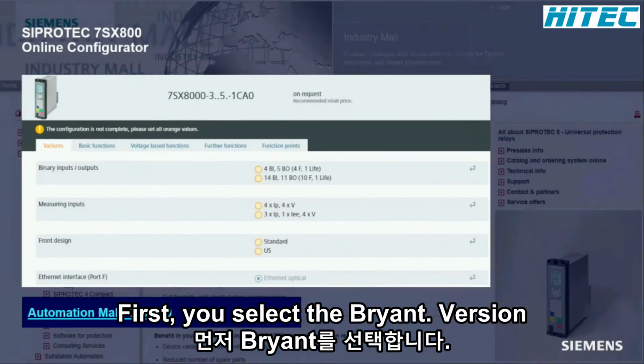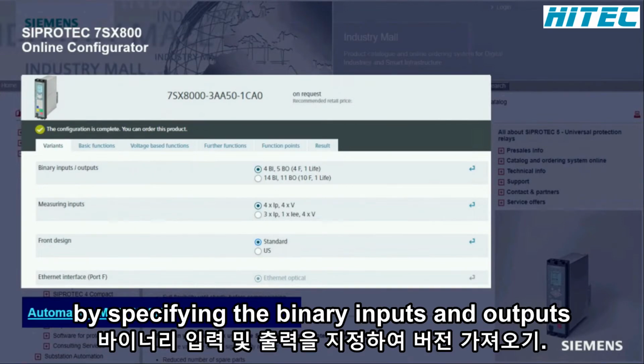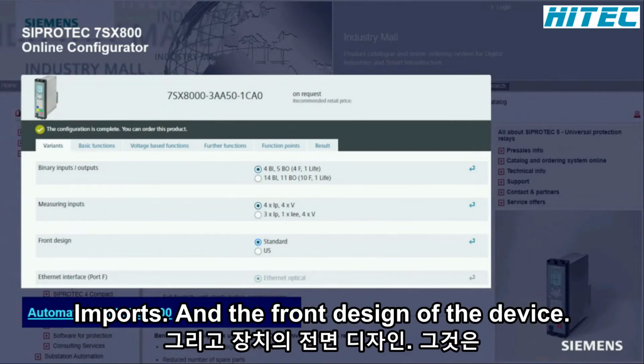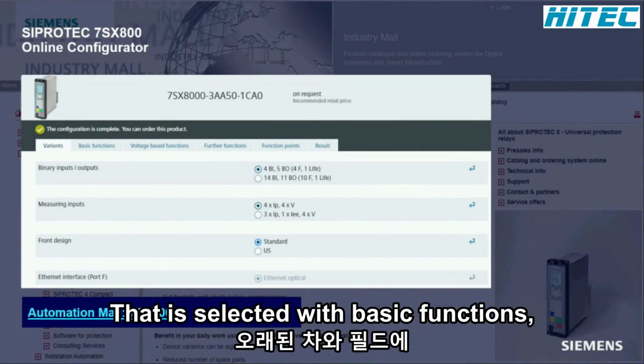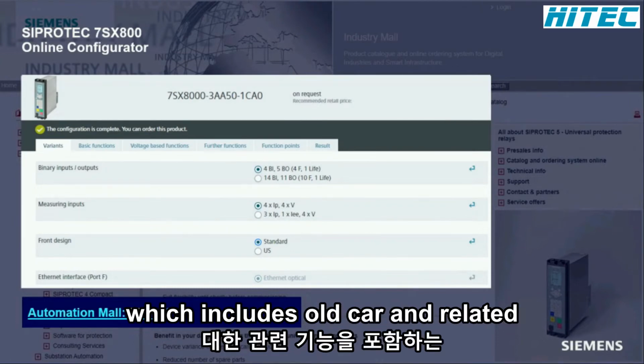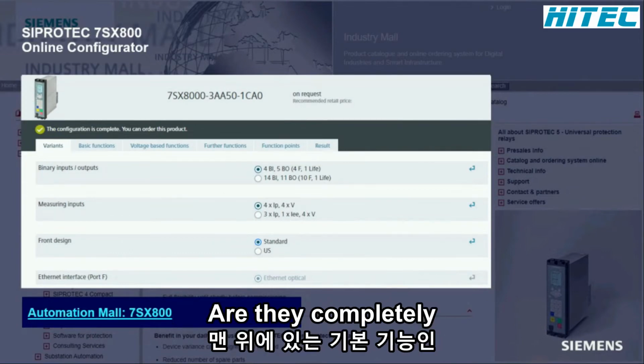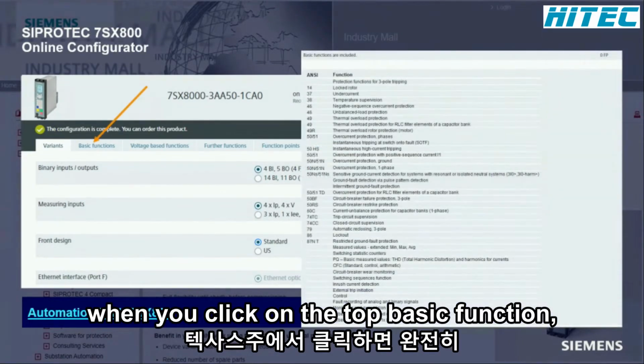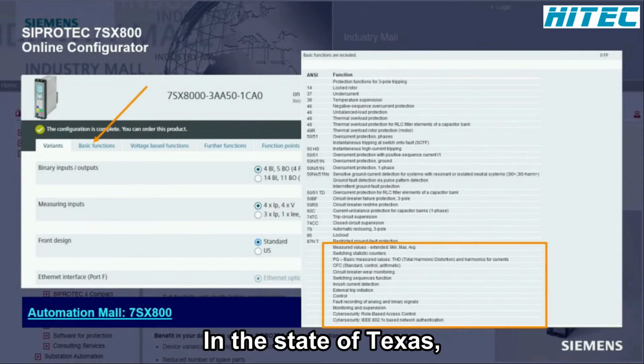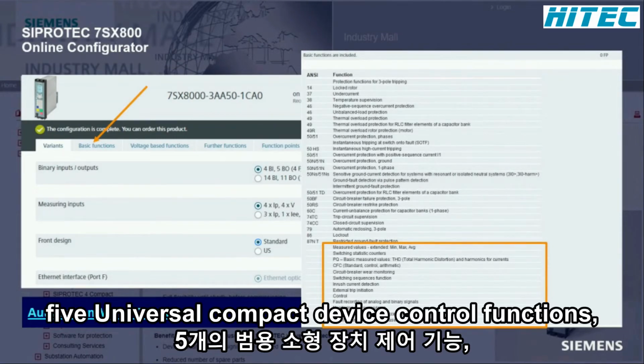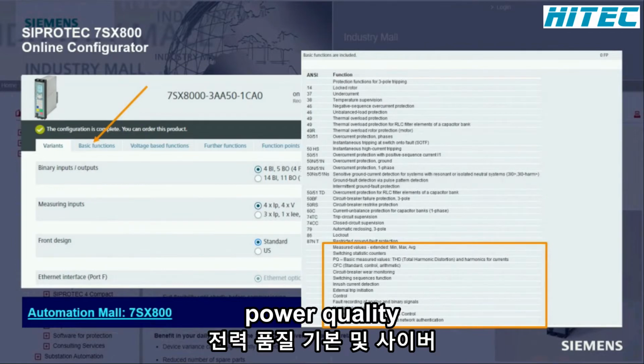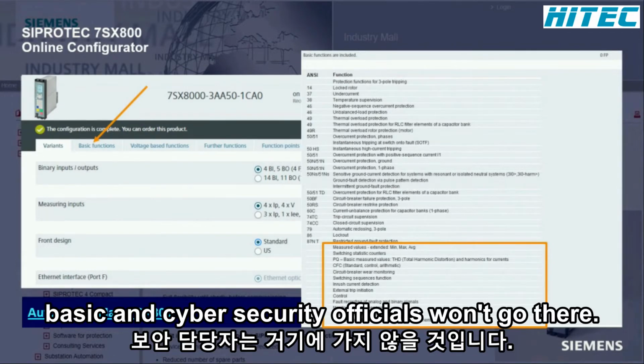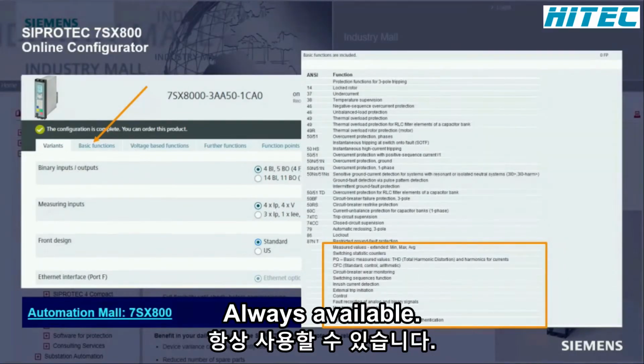First, you select the variant version by specifying the binary inputs and outputs, the measuring inputs, and the front design of the device. By default, the device is always selected with basic functions, which include all current related functions for a feeder. The complete list can be seen when you click on the tab Basic Functions. Moreover, in the SIPROTEC 5 Universal Compact Device, control functions, user logics, power quality basic, and cyber security features, among others, are always available.